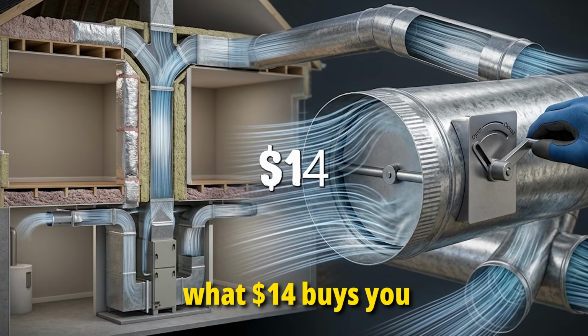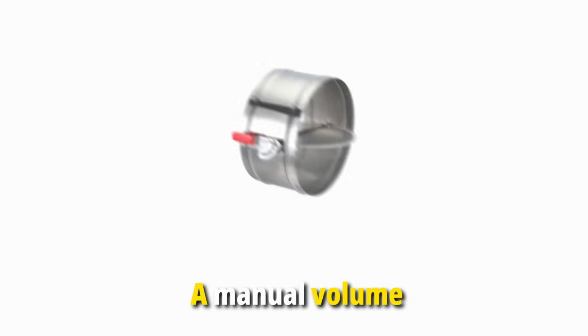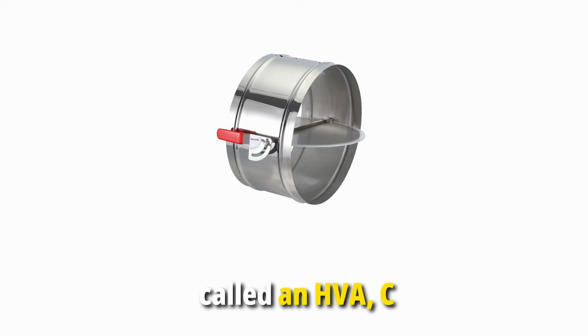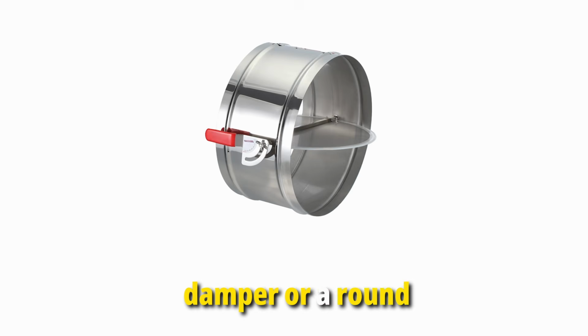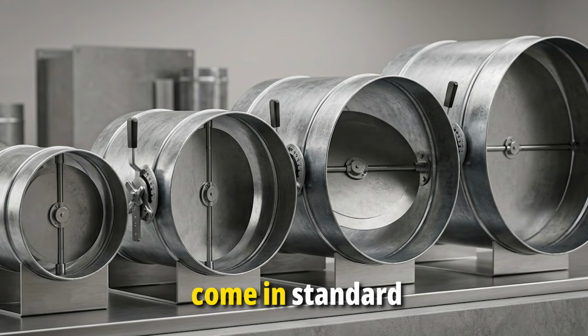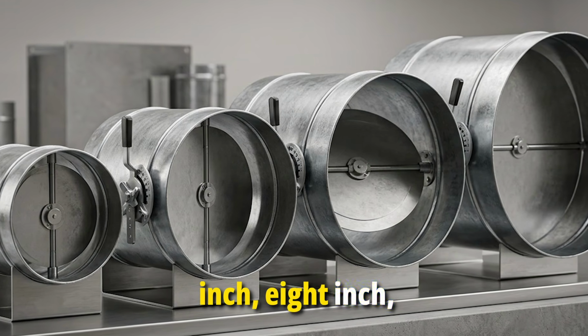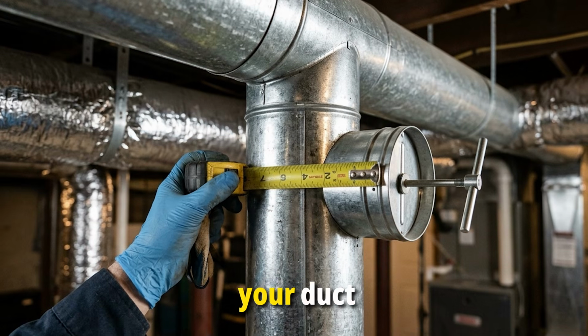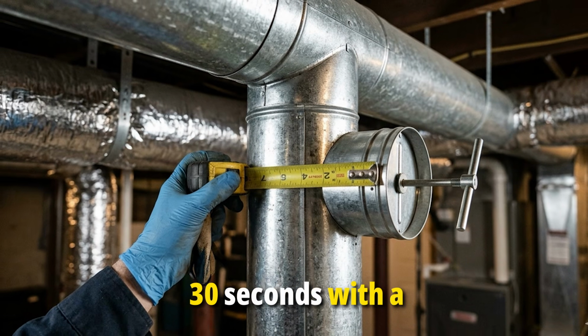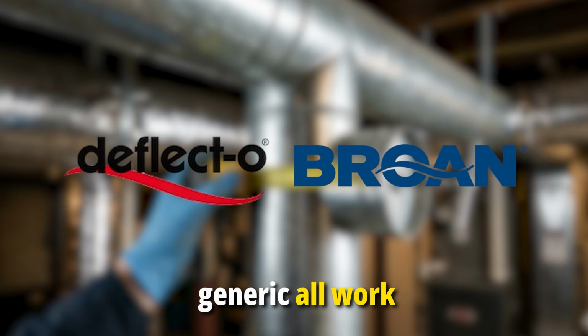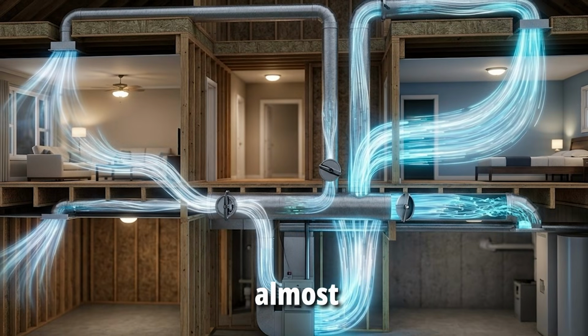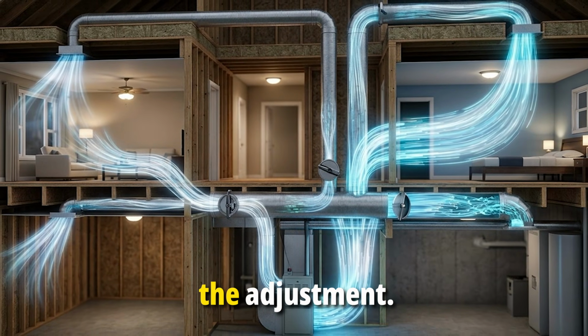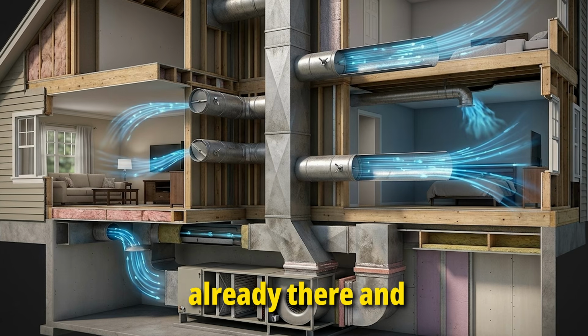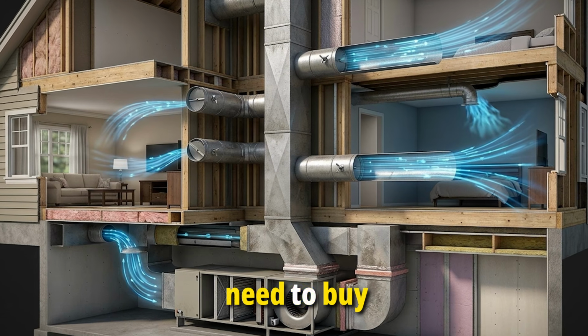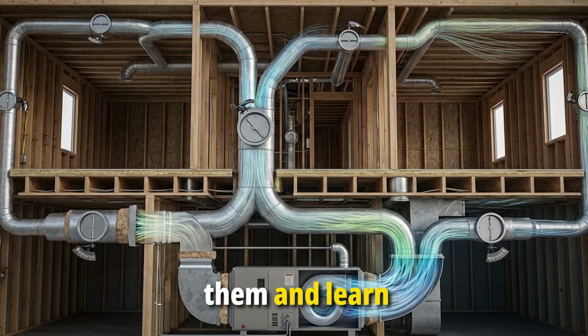Here is what $14 buys you if your system needs one added. A manual volume damper, sometimes called an HVAC branch line damper or a round duct damper. They come in standard sizes, 4-inch, 6-inch, 8-inch, 10-inch. You match the size to your duct diameter, which you can measure in about 30 seconds with a tape measure. Brands like Deflecto, Broan, or any sheet metal generic all work identically. The hardware is almost irrelevant. What matters is the adjustment. If your branch dampers are already there, and in most homes they are, you do not need to buy anything at all. You need to find them and learn how to use them.